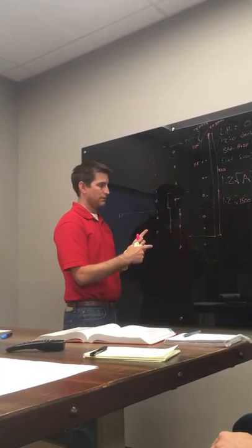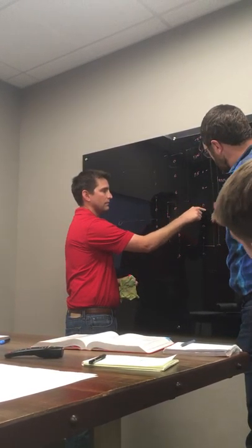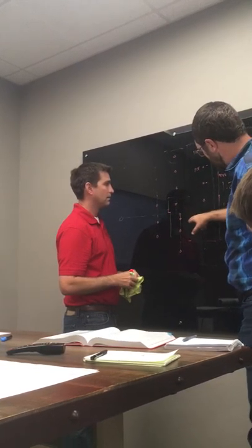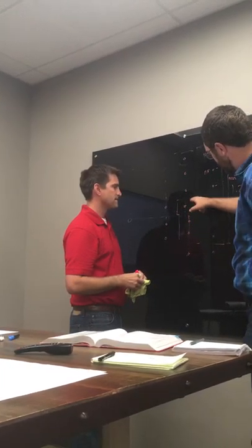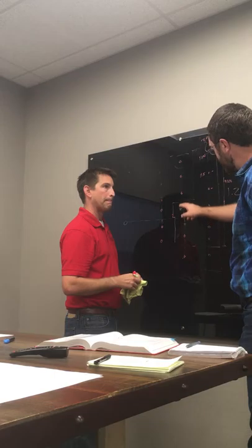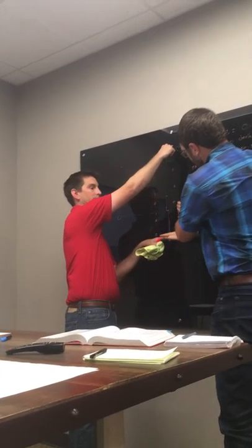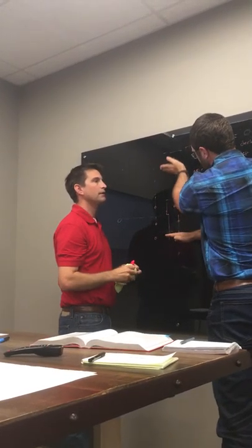Yes. Oh, one more. Yeah, I have one more. If this is your 47 foot, and then you come back to the closest to the main, and you're balancing, if you need to continue, you don't go any further this way, you just start going up this branch line? Yep. So you've already picked up your 47. And so you come down here, but then you just continue to the right hand.